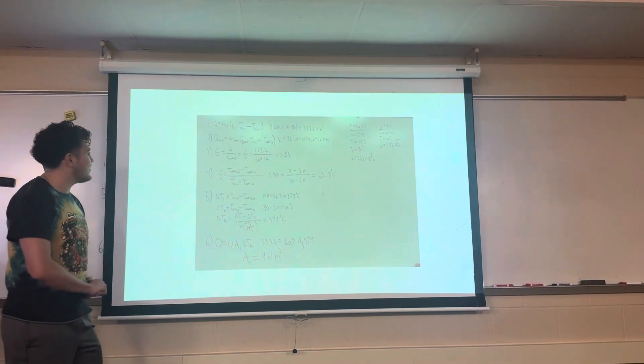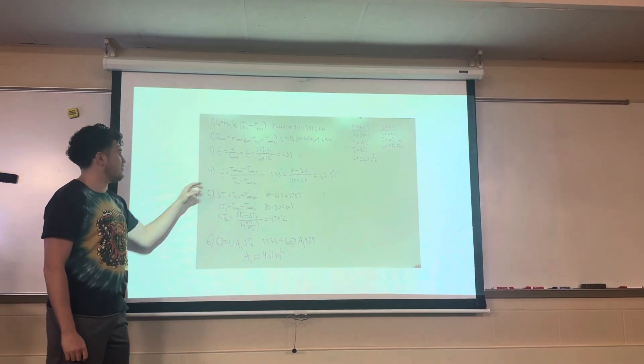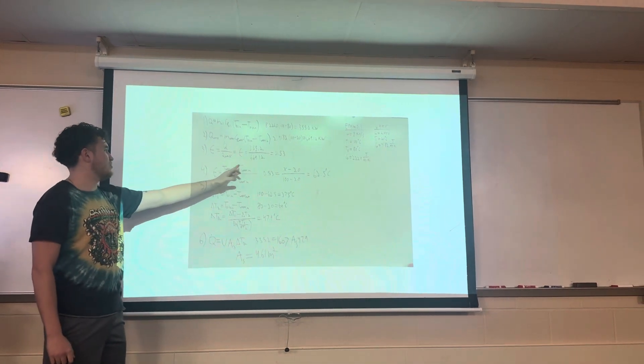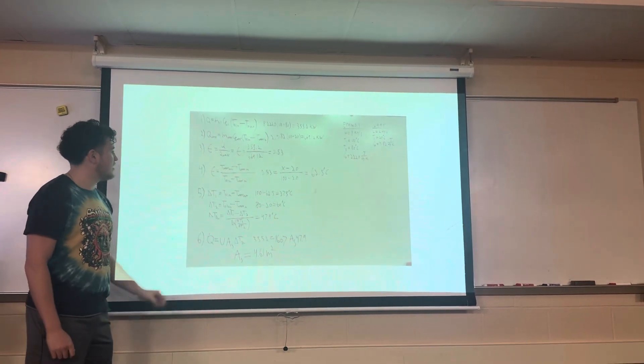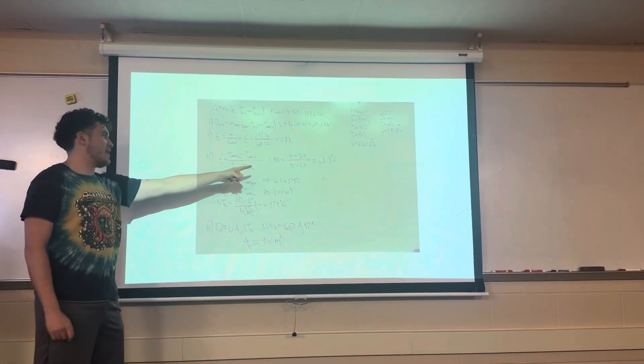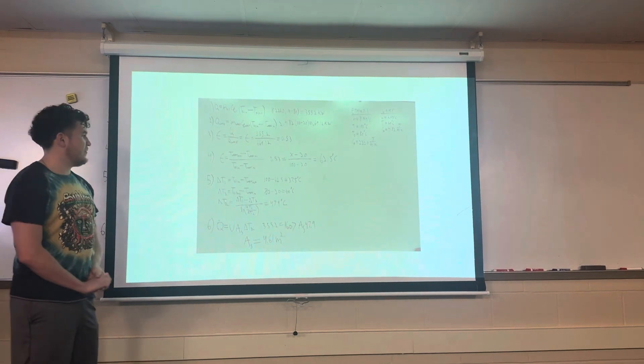Next we solve for the outlet temperature of the water. We use this equation: the effectiveness is equal to water out minus water in, over oil in minus water in. We end up with 62.5 degrees Celsius for that outlet temperature for the water.